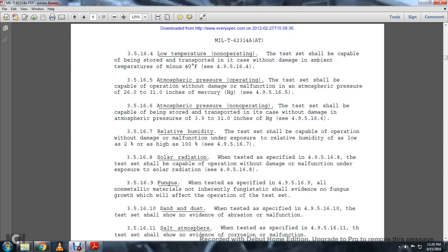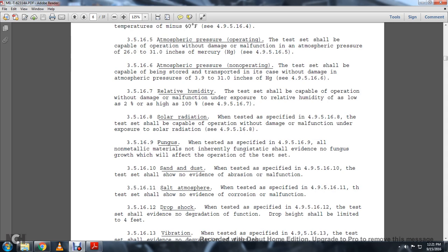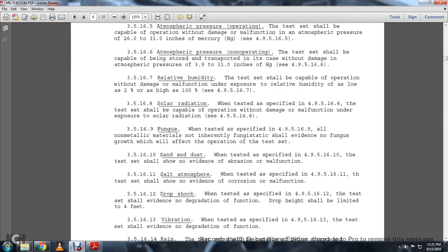3516-9, fungus. When testing specified in 495-16-9, all materials are non-inherently fungus-static. Show evidence of no fungus growth without the effect of operation of the test set. Alright, 3516-10, sand and dust. When tested as specified in 495-16-10, the test shall show no evidence of abrasion or malfunction. 3516-11, salt atmosphere. When tested in 495-16-11, the test shall have no evidence of corrosion or malfunction.